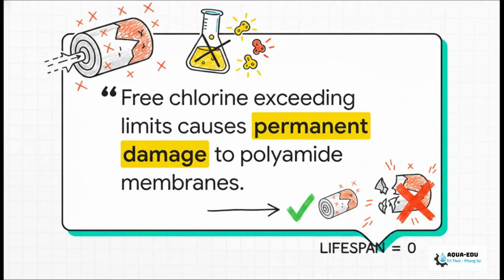So let's talk about the why. Why is this so absolutely crucial? Well, missing this step or getting this setup wrong means permanent catastrophic damage to your RO polyamide membranes. Controlling residual chlorine at the RO inlet isn't just a best practice, it's a hard requirement to protect those membranes from rapid oxidation. If we let those levels exceed the allowable limits, the damage is irreversible. We're talking membrane lifespan dropping straight to zero.